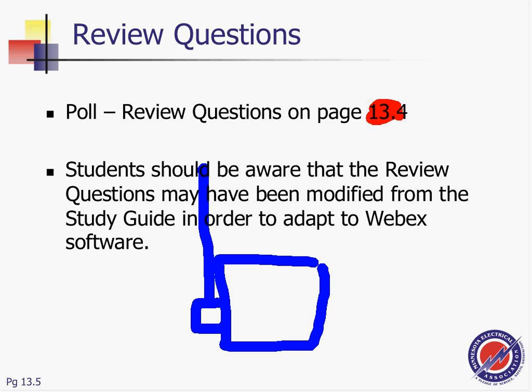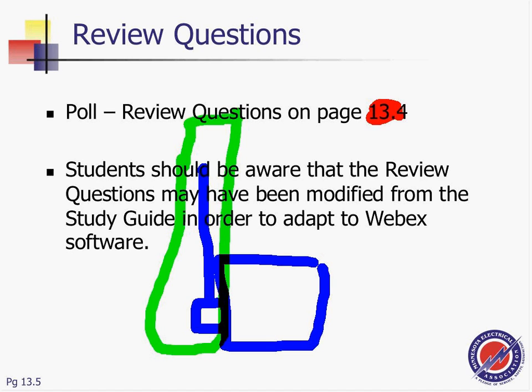In 2011, they changed this one. They say the angle connector shall not be concealed. Right now it implies that it cannot be covered, like insulated. That's in 2008. In 2009, here's how they changed it. In 2011, guys, they say no problem. You can conceal up to the connector, which means the connector itself you don't want concealed, because pulling conductors through a right angle, guys, is a pain. You can't pull it. So they said you can, as long as the angle connector is not concealed, so you can take it out, pull your conductors, and put it in again. So that was changed in 2011. But the connector shall not be concealed.